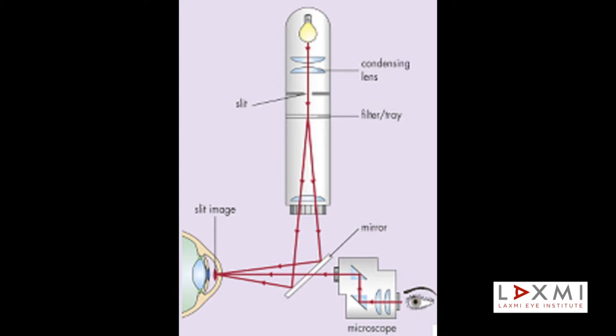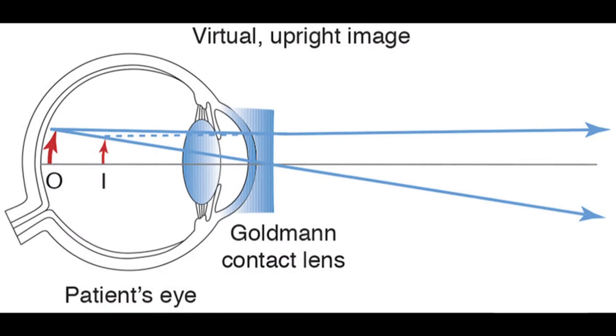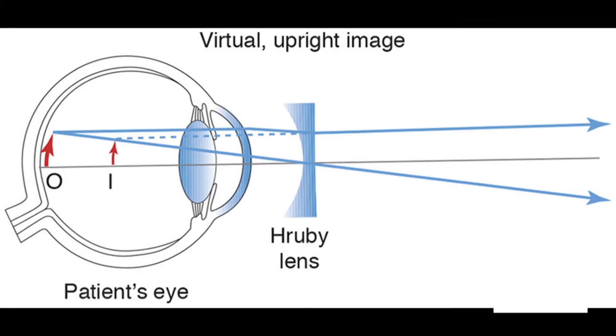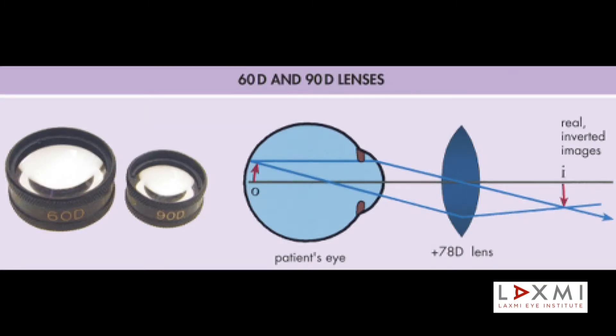Replacement of 45 diopters of corneal surface refractive power by an afocal plane surface, e.g. Goldmann lens. Neutralization of the refractive power of the eye, i.e. 60 diopters, e.g. Hruby lens. Use of indirect ophthalmoscopy principle with slit lamp, e.g. 60 diopter, 90 diopter, or 78 diopter lenses.